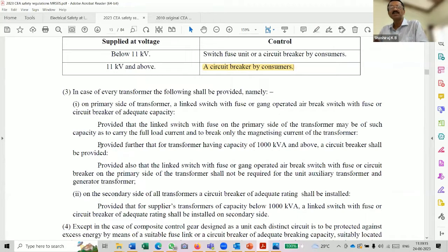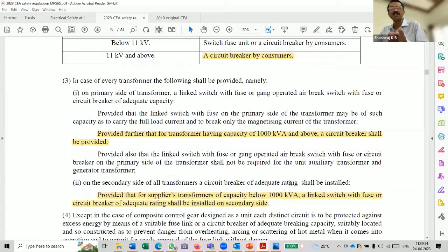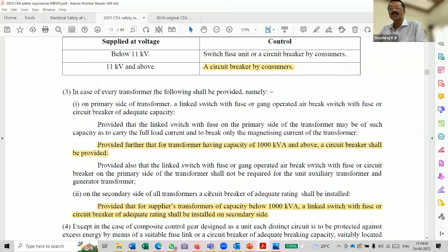The transformer means a transformer provided by a consumer as well as by a DISCOM. By default, it also goes without telling that the DISCOM stations are also included in 37.3. And here there is a specific requirement in 37.3.2, where for a supplier's installation, the secondary protection up to 1000 kVA is exempted from a breaker, and only beyond 1000 it is required.